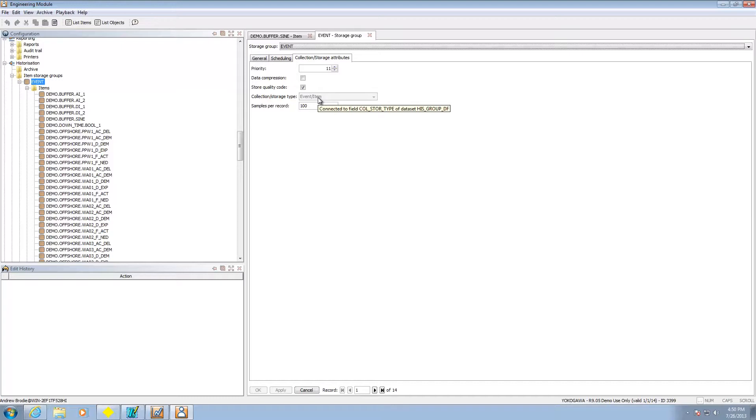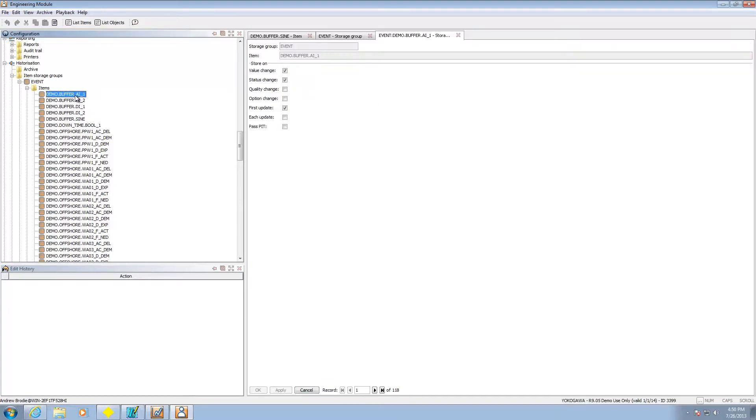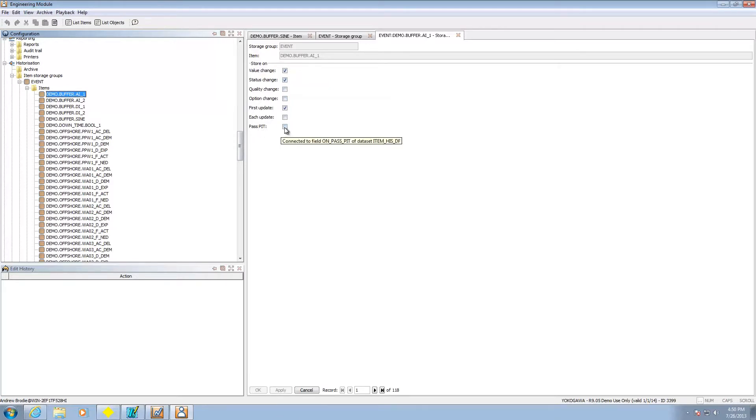In this case event item is going to open up underneath the actual items certain things that we can store based on. Remember I was talking about the PIT filter. This is where we pick that PIT filter to allow you to do storage based on certain dead bands and values exceeding certain measures over time.